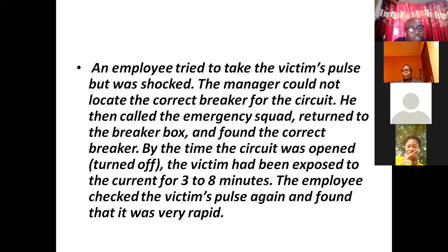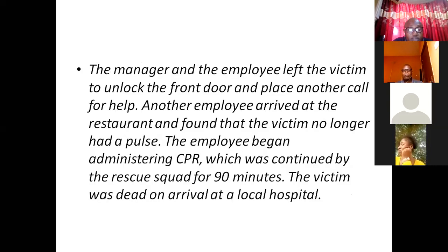He got shocked. When he got shocked, one of the employees who wanted to save him just went straight after him. That one also got shocked because there was still current in his body. They were checking around for the circuit breaker, but they could not locate the correct one. Before they located it, the victim had been exposed to current for 3 to 8 minutes. By the time they called emergency people and took him to the hospital, he had given up the ghost.